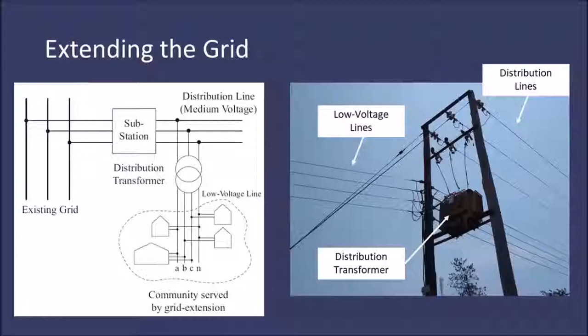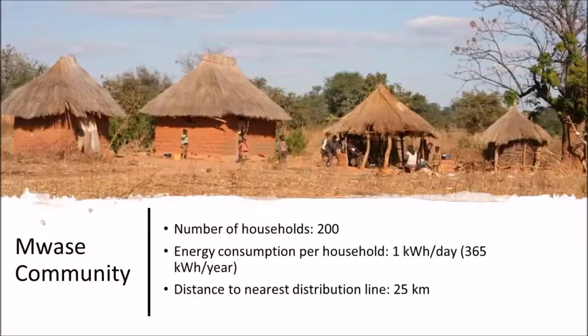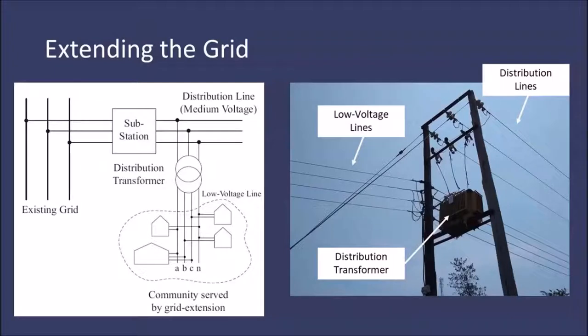We'll assume Mwase is about 25 kilometers from the nearest distribution line. If we wanted to consider a grid extension approach to electrifying Mwase, it would involve connecting to the existing distribution line, shown on the left. We'd probably have to add a substation to connect the two lines, build a new distribution line, and then at Mwase connect distribution transformers, which reduce the voltage to about 400 volts, and then connect the individual households from that.